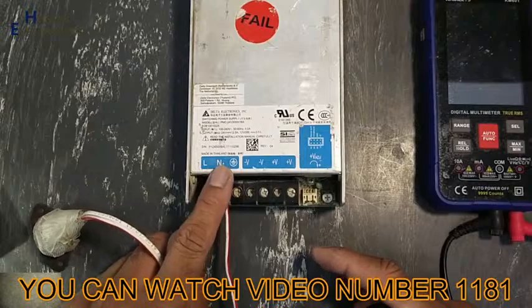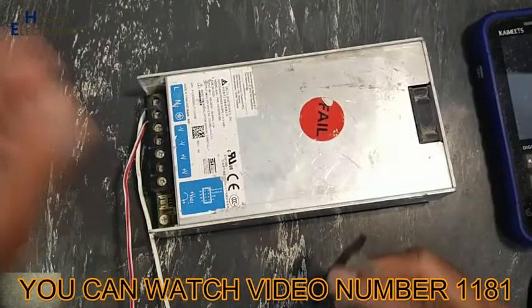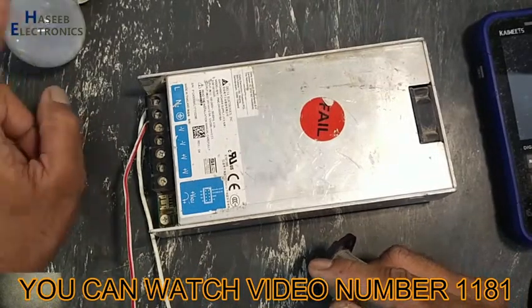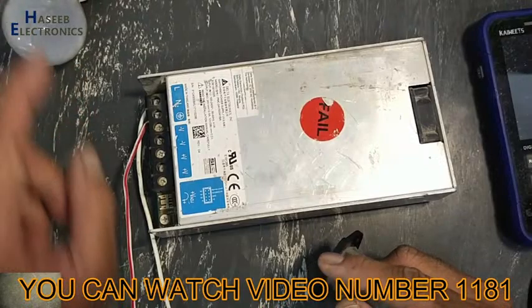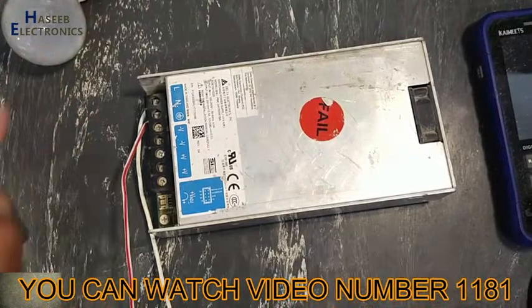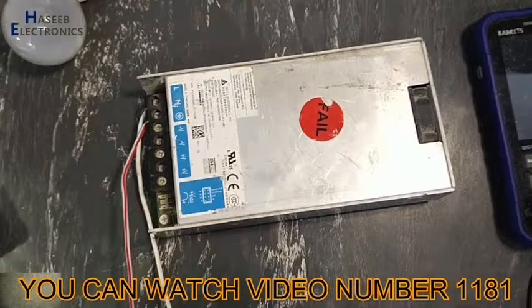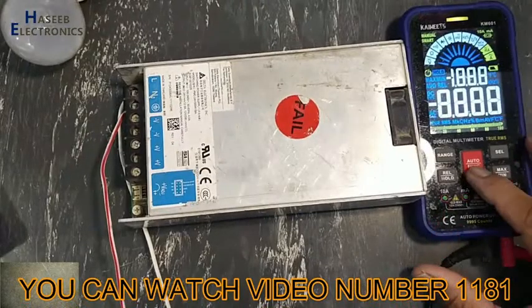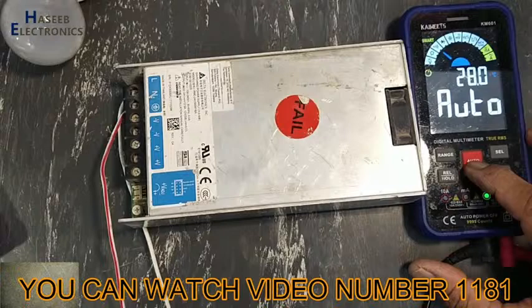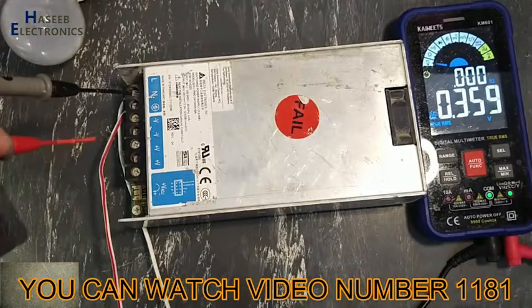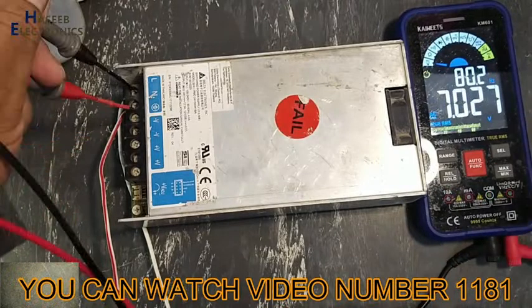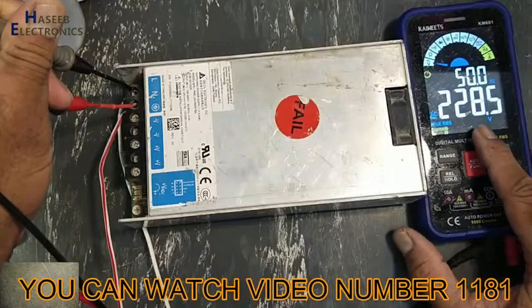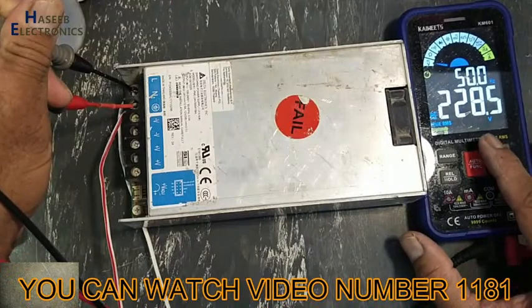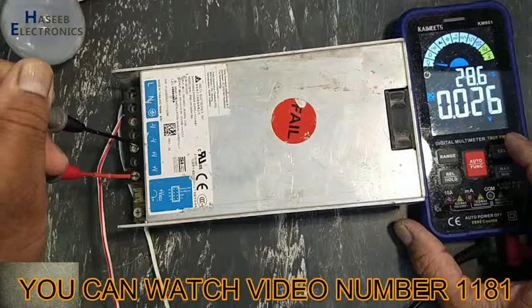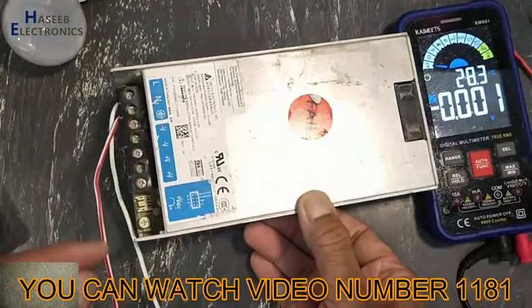Line neutral. I will apply power using a series lamp and we will monitor the lamp condition. There is no indication on the lamp. Set the multimeter to AC. 228 volts. If we check the output, there is no output and the LED is off.